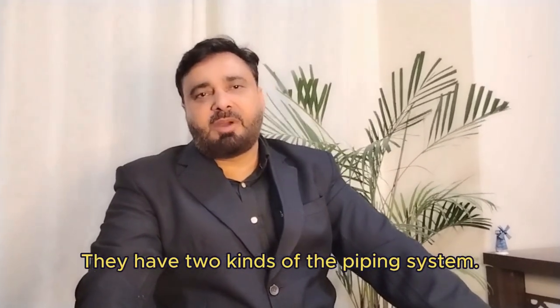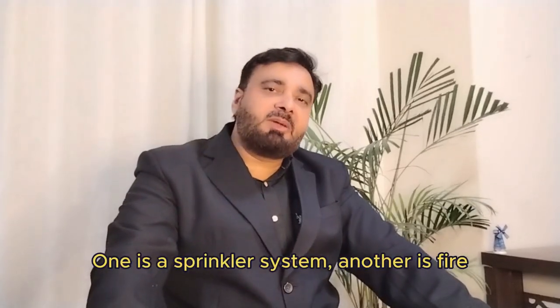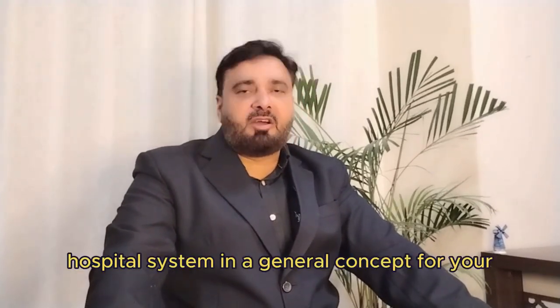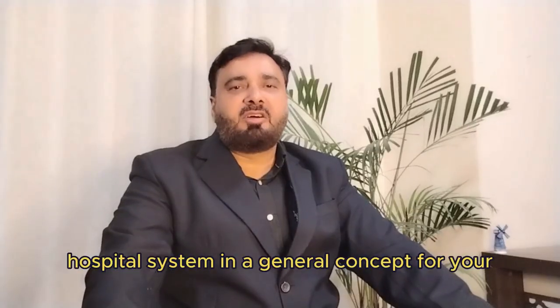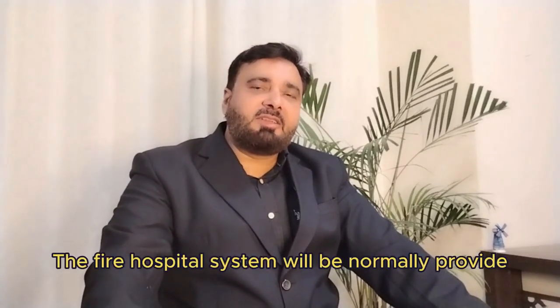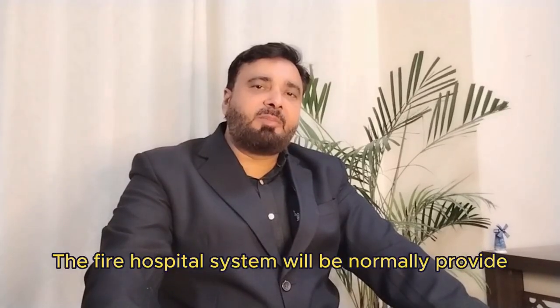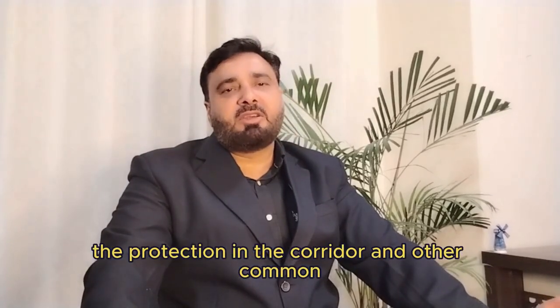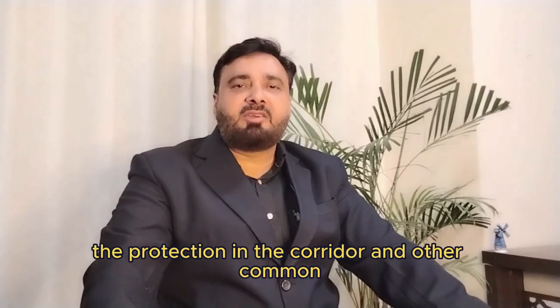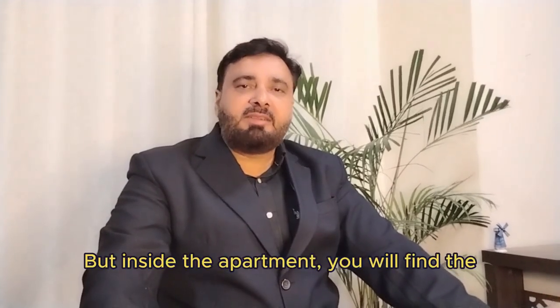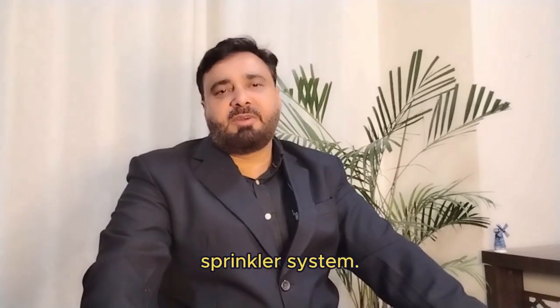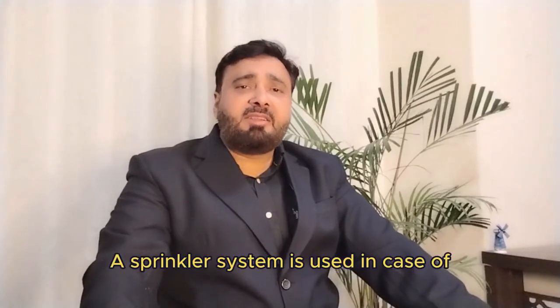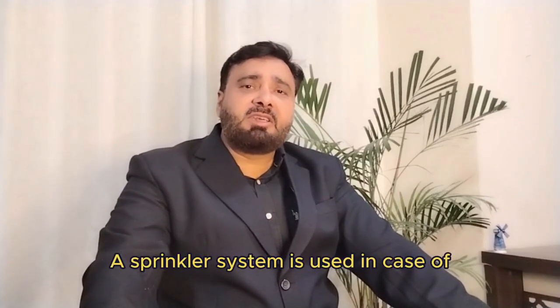They have two kinds of piping system. One is the sprinkler system, another is the fire hose system. As a general concept for your understanding, the fire hose reel system will normally provide the protection in the corridor and other common areas, but inside the apartment you will find the sprinkler system. A sprinkler system is used in case of fire.